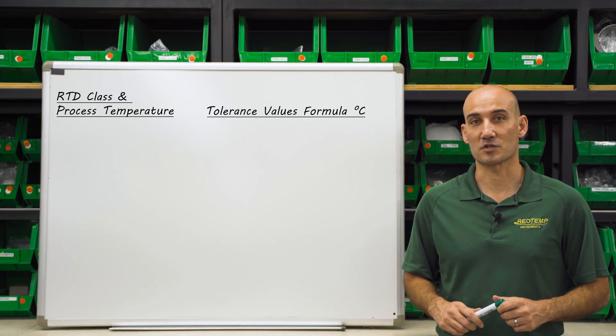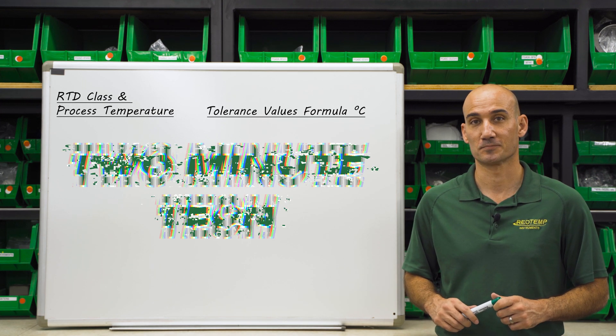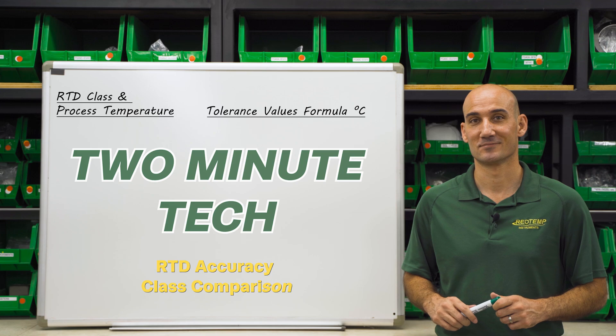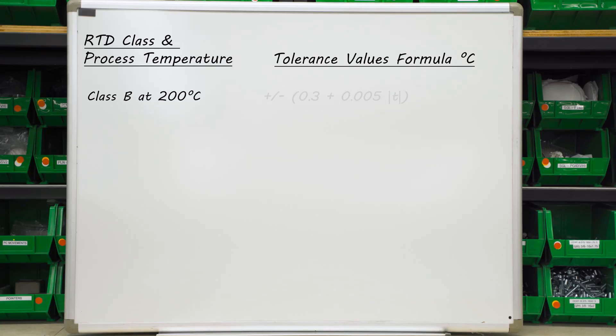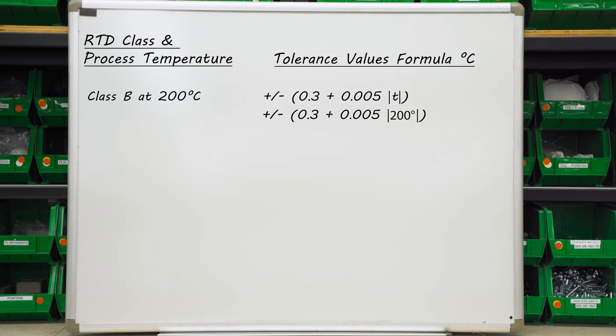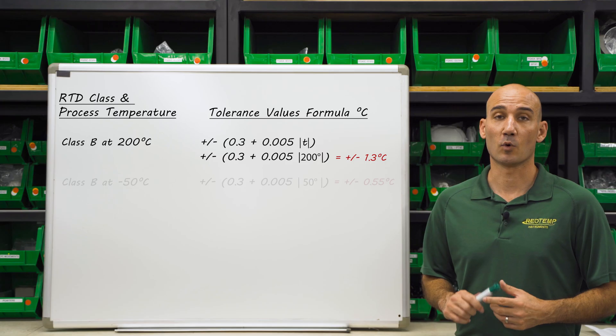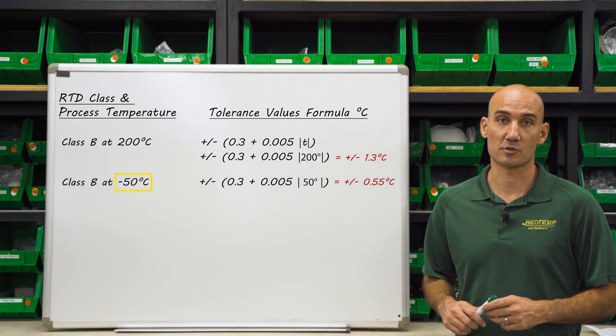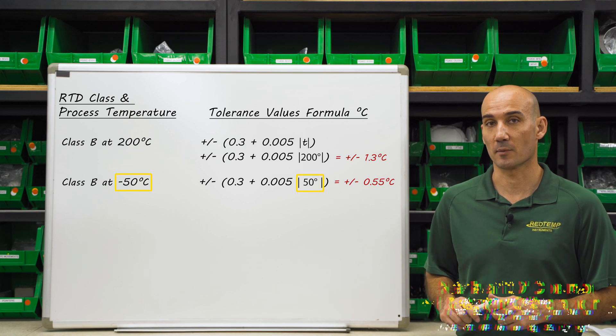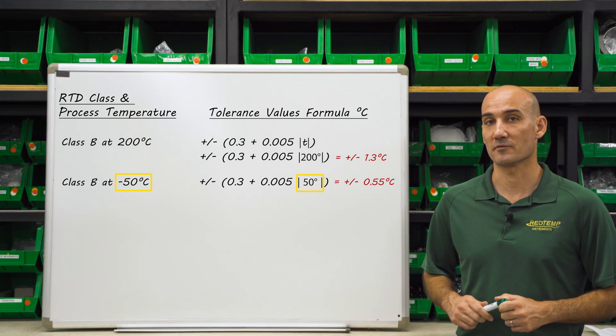For example, let's look at the accuracy of a class B RTD at 200 degrees Celsius. In the formula, T equals our absolute temperature in degrees Celsius. So we take 200 times 0.005 plus 0.3, which equals plus or minus 1.3 degrees Celsius. If you want to know the accuracy of a negative temperature, keep in mind that the formula uses absolute temperature, so you would enter it as a positive number.